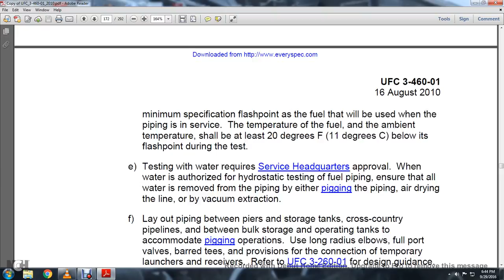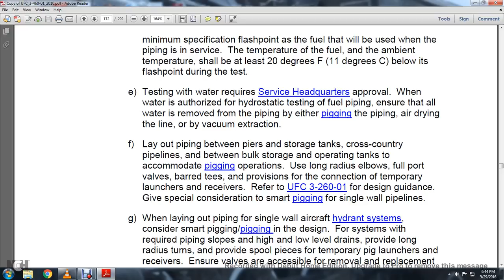Lay out piping between the piers and the storage tank, and cross country pipelines between the bulk storage and operation tank, to accommodate pigging operations using long radius elbows, full port valves, and barred tees to provide for the connection of temporary launchers and receivers. Refer to UFC 3-260-01 for design guidance that gives special consideration of smart pigging for single wall pipelines.